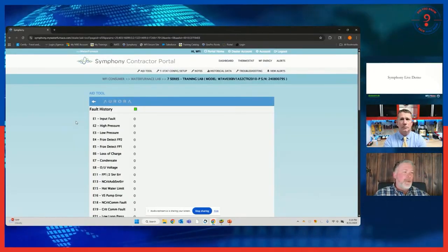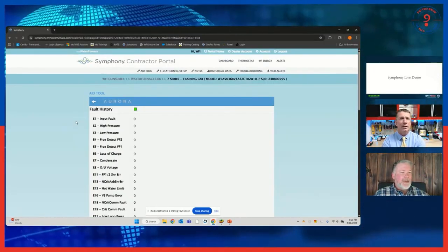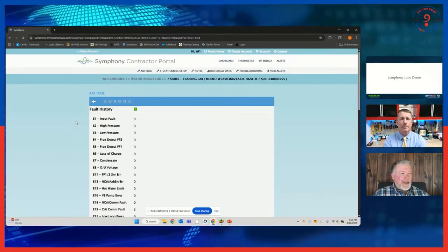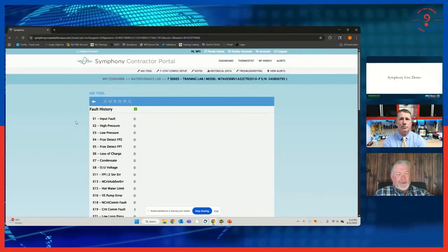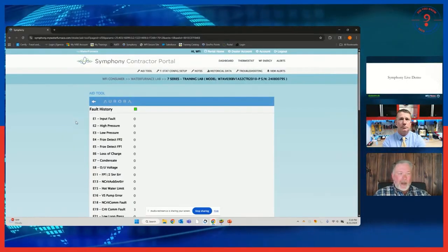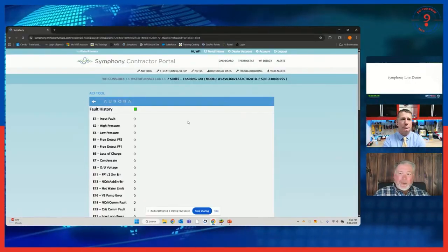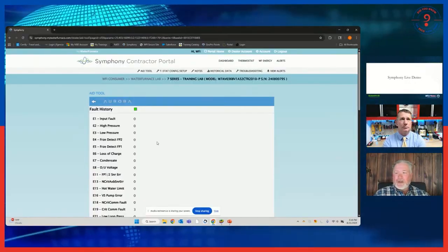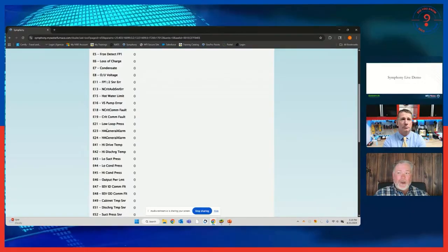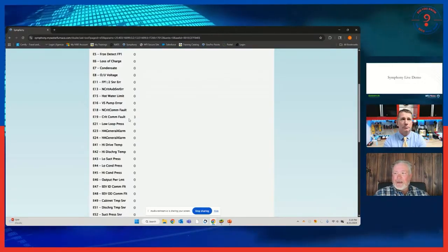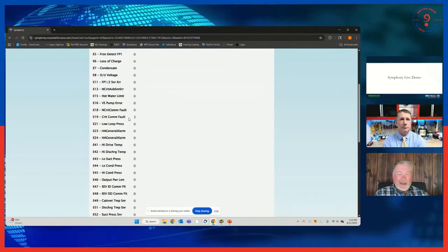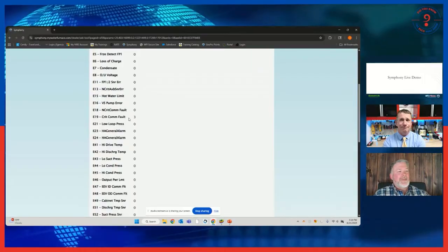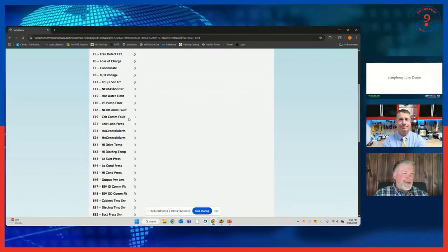So if it's something like a low pressure fault, for example, it may just be an anomaly, so we have like a 3-time fault - once it hits that third time, it'll lock the unit down. So if I'm doing a diagnosis, I can come down here and just see what it is. This unit, for example, has had 3 critical communication faults, which tells me it's had issues talking to the thermostat.